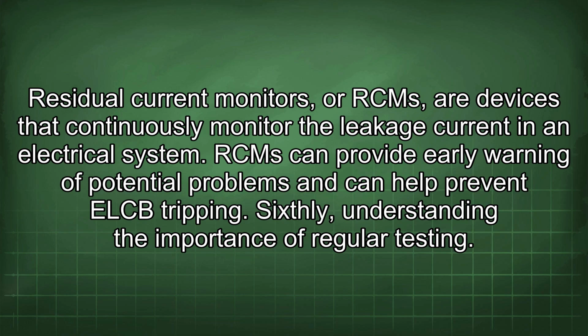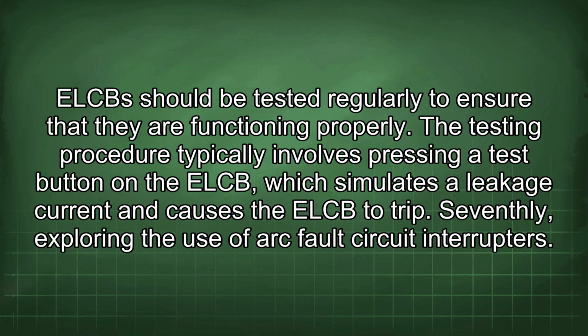Sixthly, understanding the importance of regular testing. ELCBs should be tested regularly to ensure that they are functioning properly. The testing procedure typically involves pressing a test button on the ELCB, which simulates a leakage current and causes the ELCB to trip. Seventhly, exploring the use of arc fault circuit interrupters.